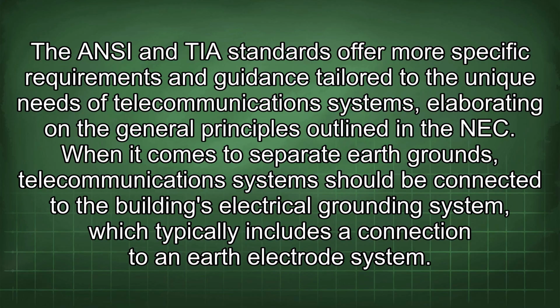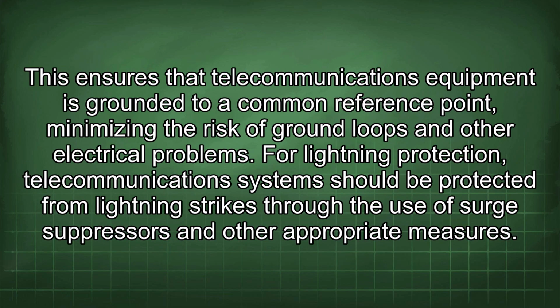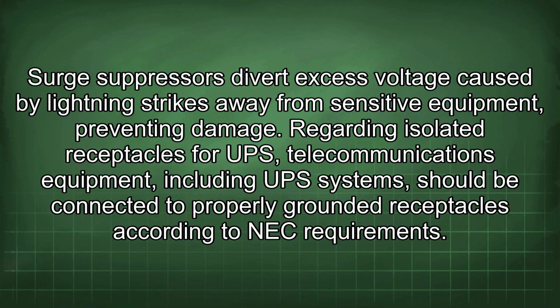When it comes to separate earth ground, telecommunications systems should be connected to the building's electrical grounding system, which typically includes a connection to an earth electrode system. This ensures that telecommunications equipment is grounded to a common reference point, minimizing the risk of ground loops and other electrical problems. For lightning protection, telecommunications systems should be protected from lightning strikes through the use of surge suppressors and other appropriate measures. Surge suppressors divert excess voltage caused by lightning strikes away from sensitive equipment, preventing damage.